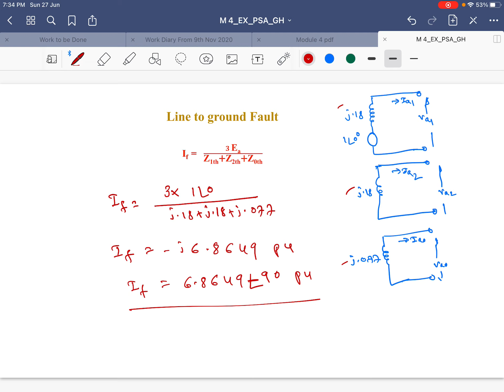Very simple. Then for the line to line fault, just substitute the values in this. Once again, a squared is 1 angle of 240 minus 1 angle of 120. EA is 1 angle of 0. ZTH1 is J0.18, ZTH2 is also J0.18. Then if you calculate for this, it is minus J4.8111 per unit. This is the fault current in the case of line to line fault, either IB or minus IC.